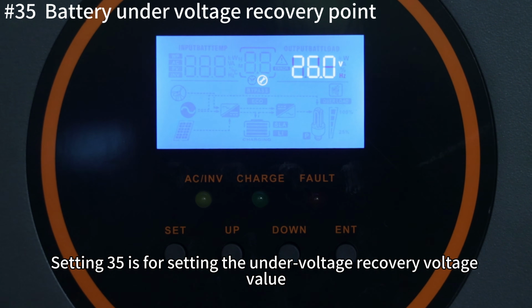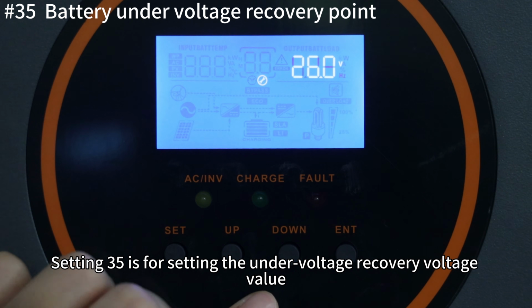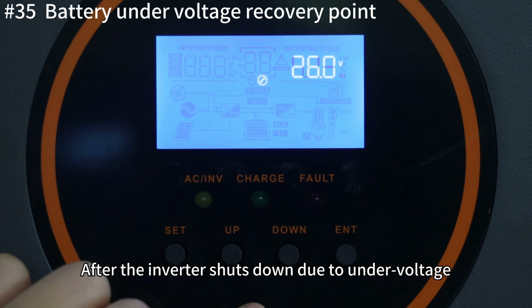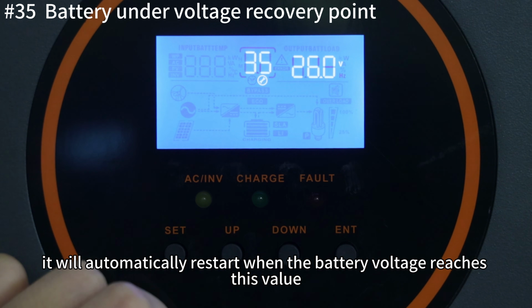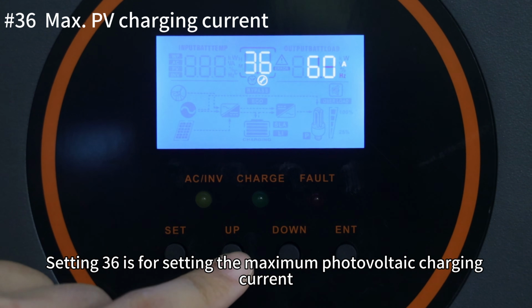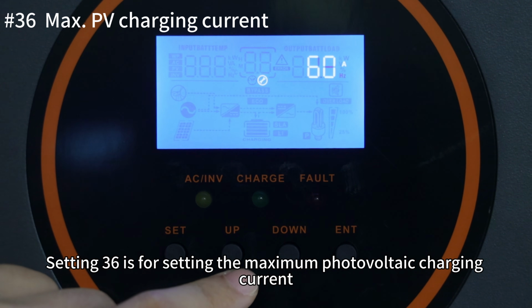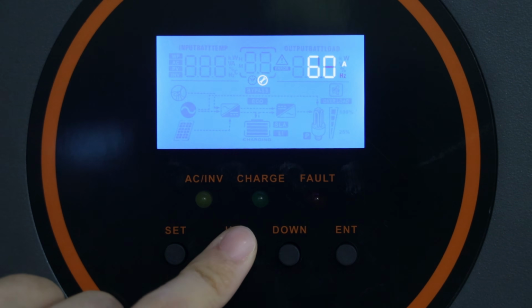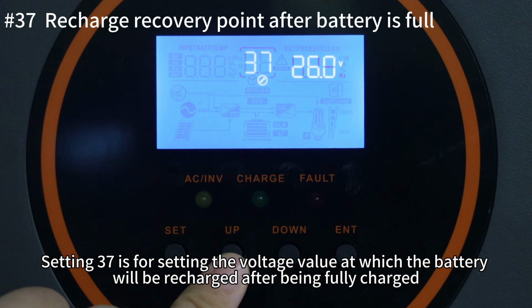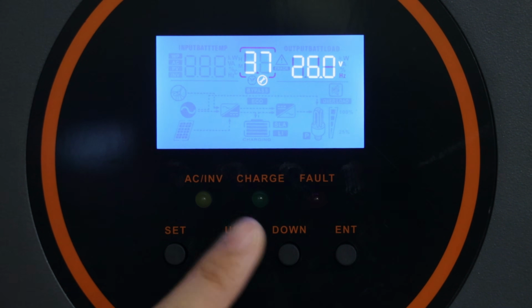Setting 35 is for setting the undervoltage recovery voltage value. After the inverter shuts down due to undervoltage, it will automatically restart when the battery voltage reaches this value. Setting 36 is for setting the maximum photovoltaic charging current. Setting 37 is for setting the voltage value at which the battery will be recharged after being fully charged.